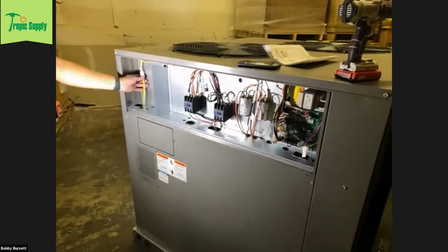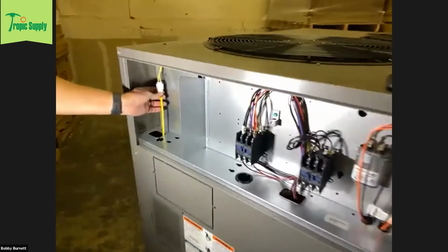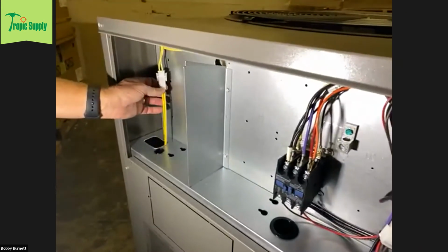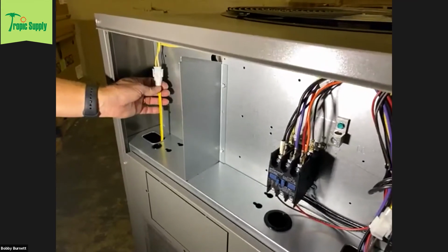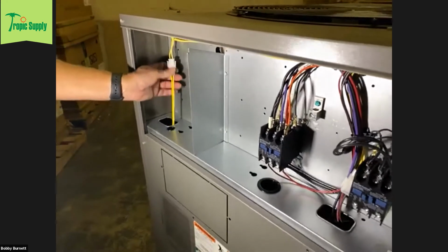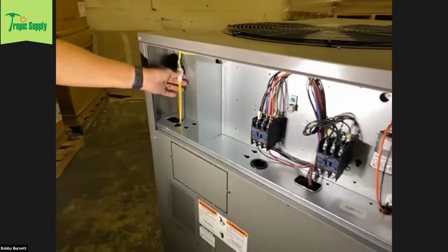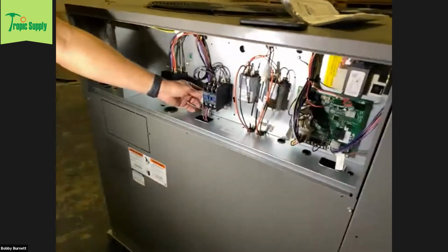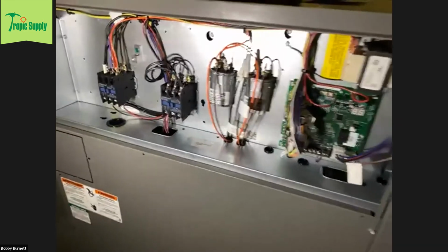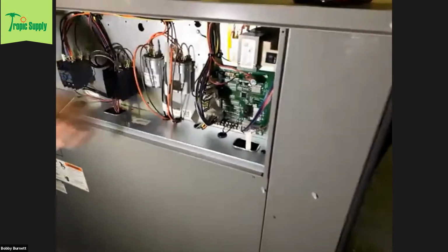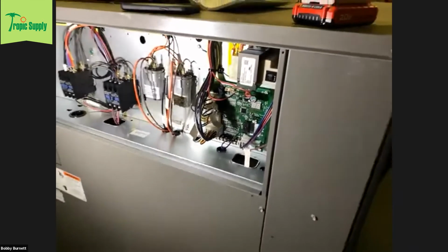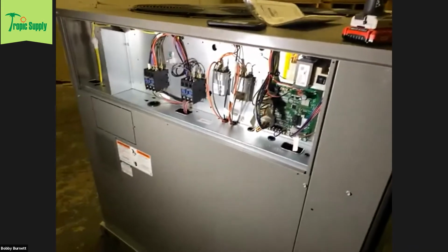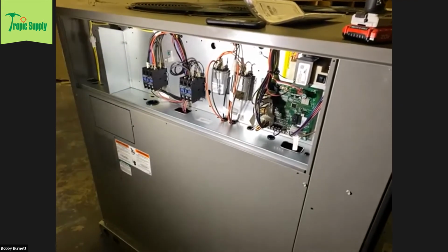While we're over here, you'll see we have several connectors that allow you to troubleshoot the high and low pressure switches just by unclipping the switches and checking them here. There's the one for low pressure, that's the one for high pressure. You've got fan motor connections you can do the same with, so it makes it easier to troubleshoot the electrical on those units.